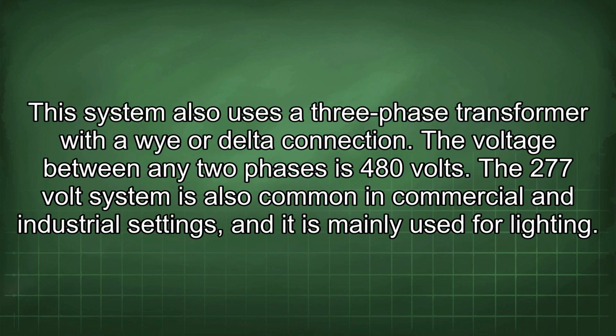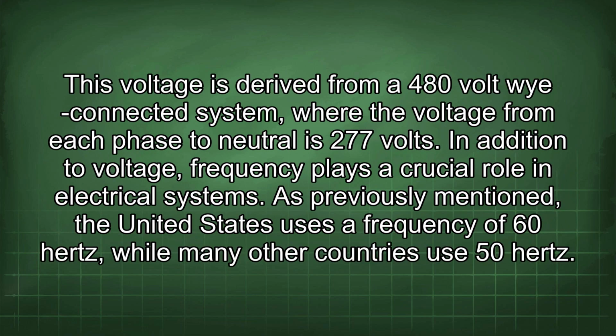This system also uses a three-phase transformer with a Y or delta connection. The voltage between any two phases is 480 volts. The 277-volt system is also common in commercial and industrial settings, and it is mainly used for lighting. This voltage is derived from a 480-volt Y-connected system, where the voltage from each phase to neutral is 277 volts.